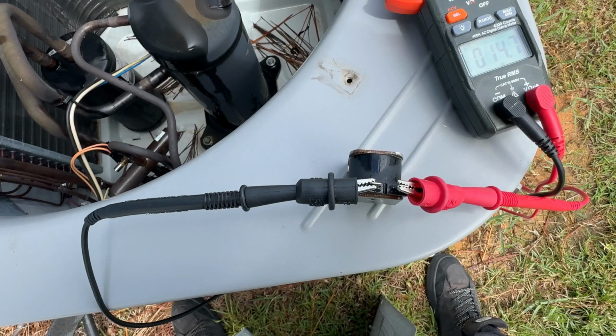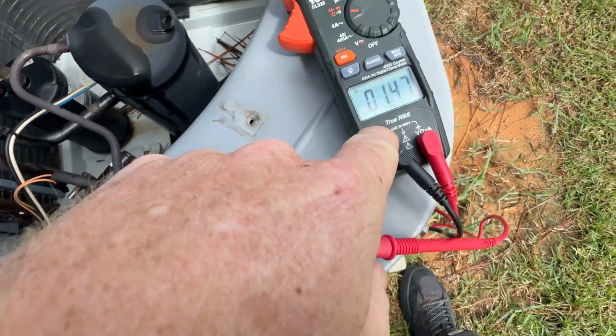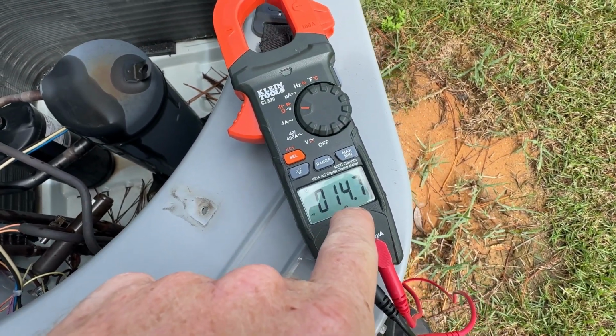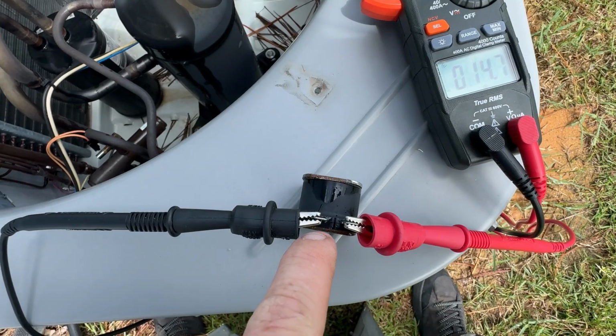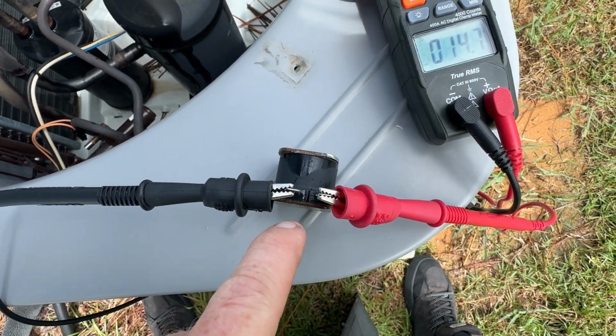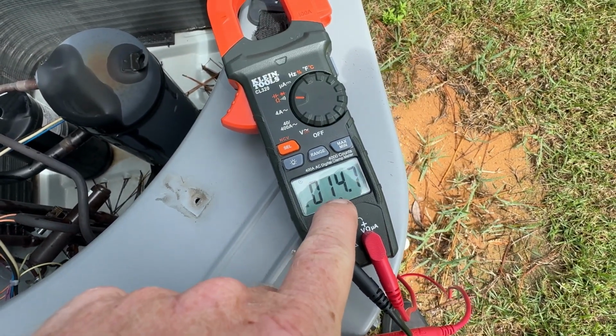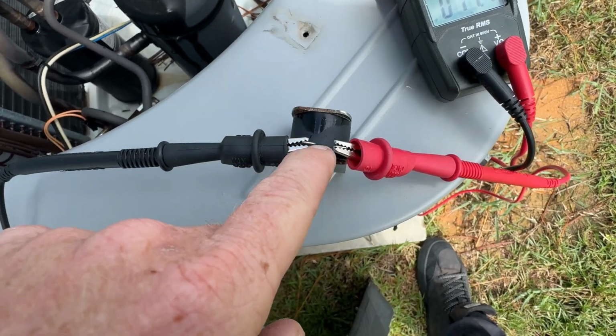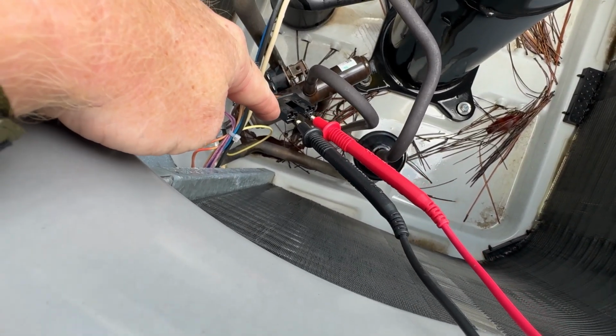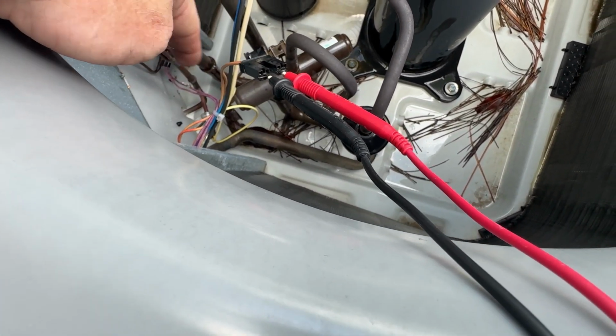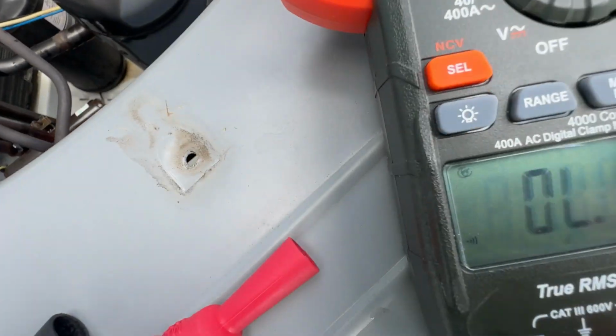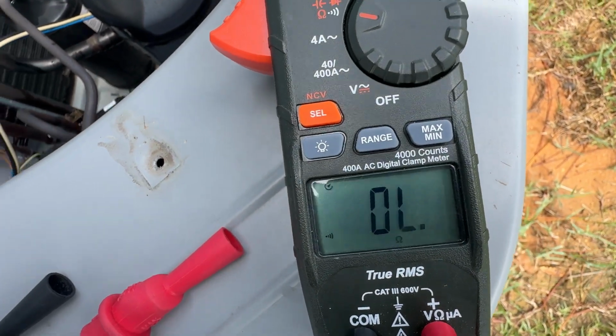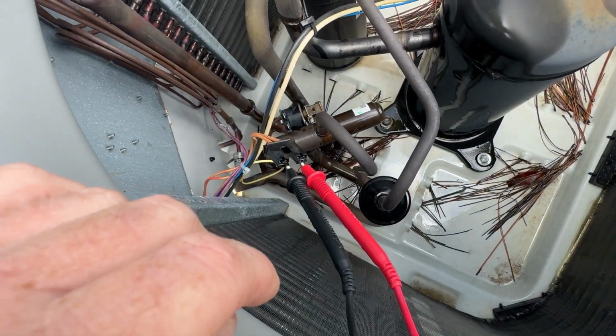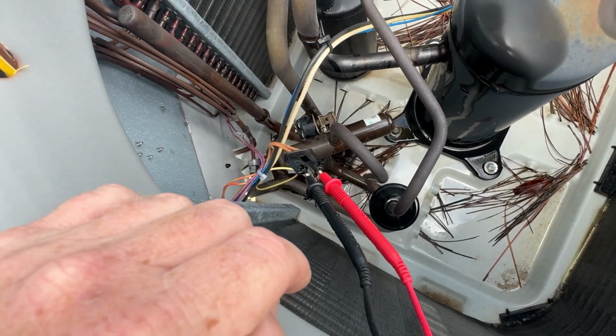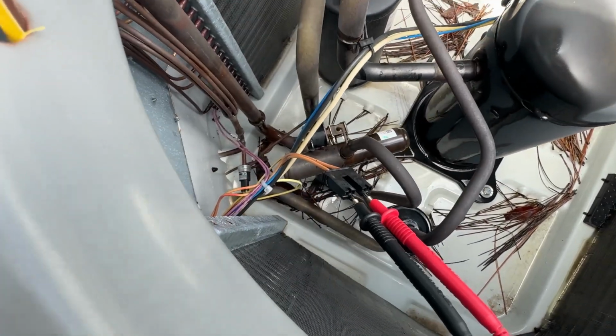All right, so the solenoid, I'll ohm out across here, and you should get 10 to 20, just like a contactor coil. So this is testing good. So this component looks like it's good. We're gonna put it back on this. So now I'm ohming out the plug resistance on each side, going back, and you should have OL, which we do have. So now we're gonna ohm everything out to ground and see if something's shorted to ground.